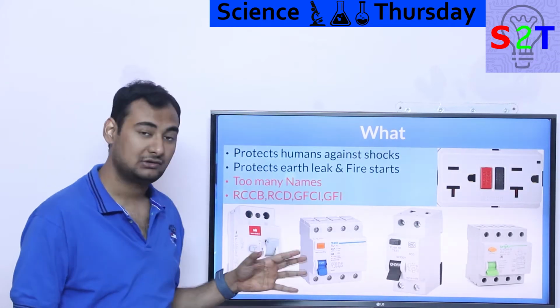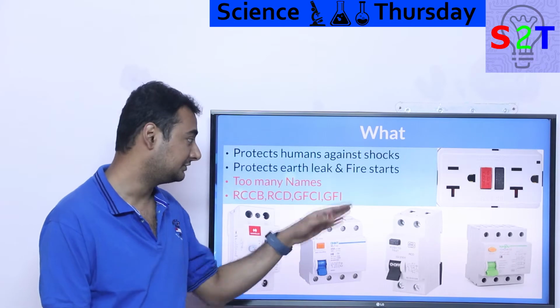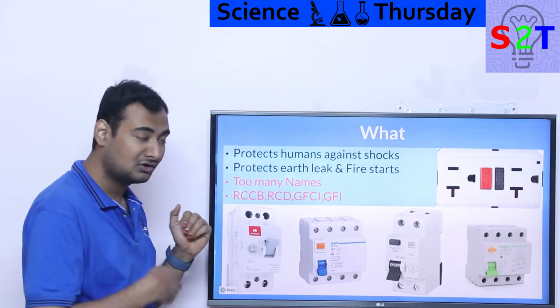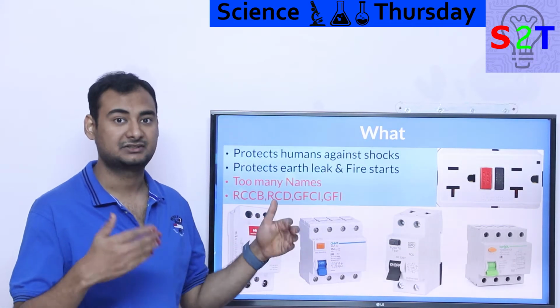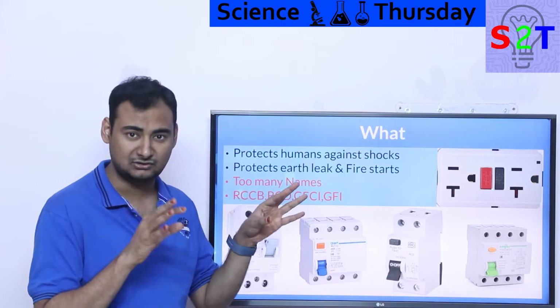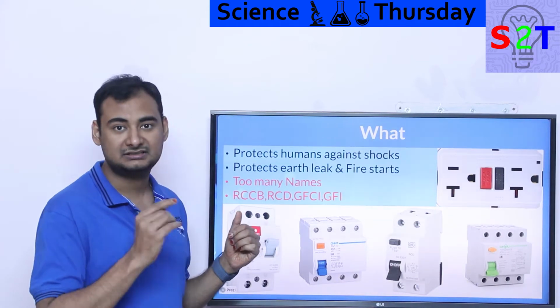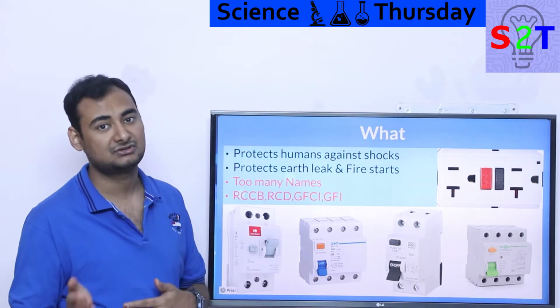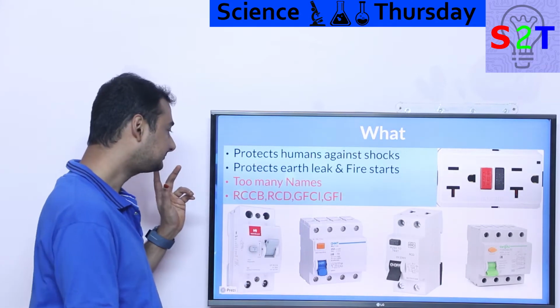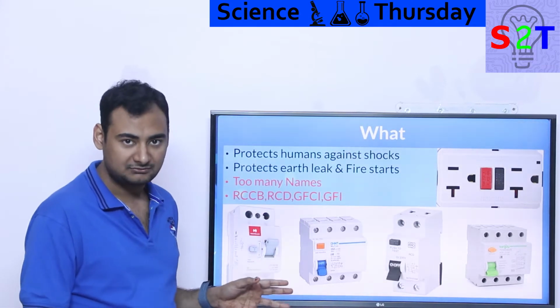So this device also helps as an extra layer of protection against fire starters, because not every electrical fire starts through electrical arcing. Sometimes it happens as a slow burn. So in that slow burn, if you could have detected the earth leakage, you could have stopped it. This puppy does that. Now, there is one severe problem with this equipment.